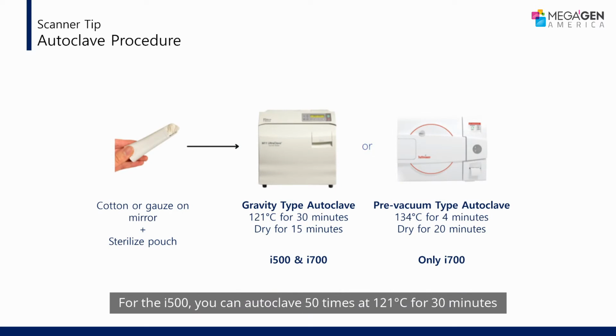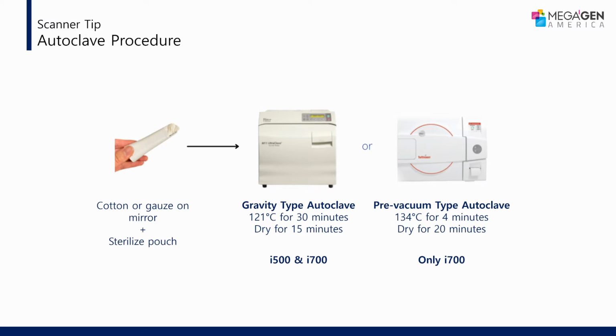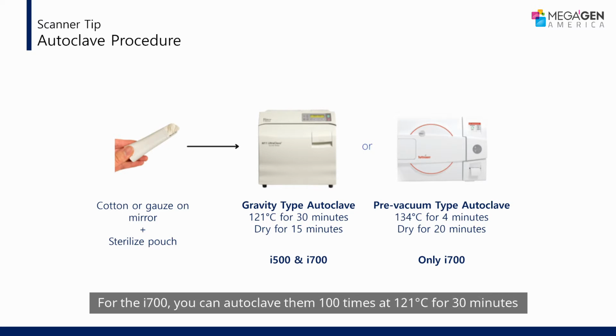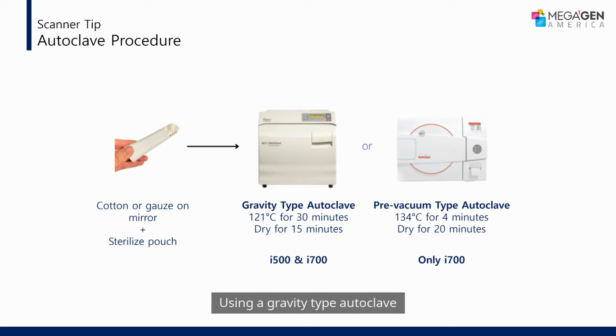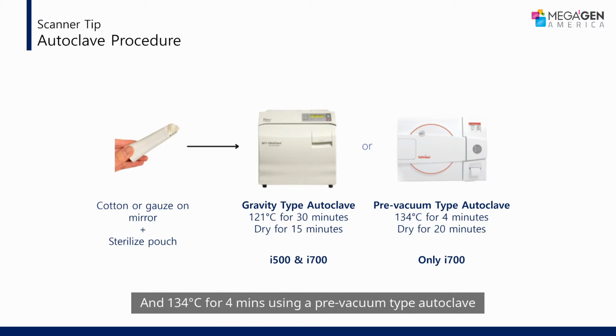For the i500, you can autoclave 50 times at 121 degrees Celsius for 30 minutes. For the i700, you can autoclave them 100 times at 121 degrees Celsius for 30 minutes using a gravity-type autoclave, and 134 degrees Celsius for 4 minutes using a pre-vacuum type autoclave.